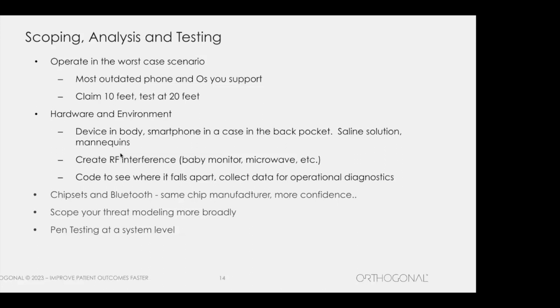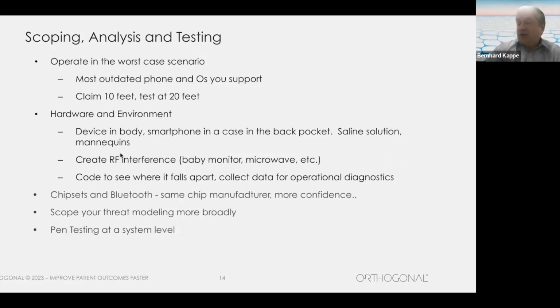Great. So obviously, part of what you need to do is verify that you have good security controls, right? And for your claims as well, and how your device is supposed to work. So what the FDA has told us really is operate on the worst case scenarios. And from talking to lots of device manufacturers as well, if you're testing, test on the most outdated phone that you support and the most outdated operating system you support.